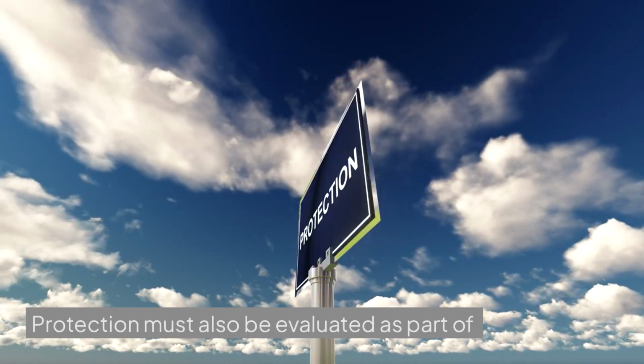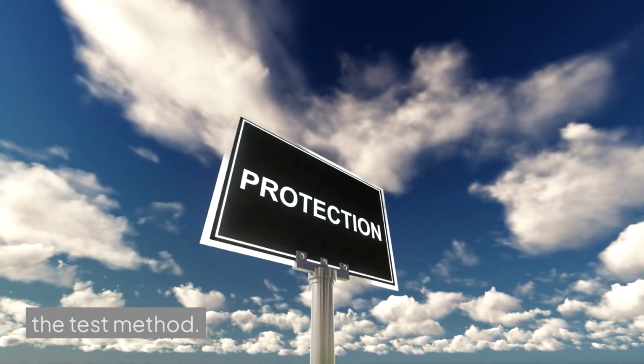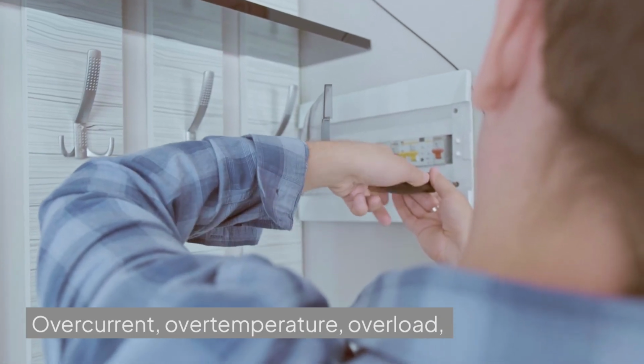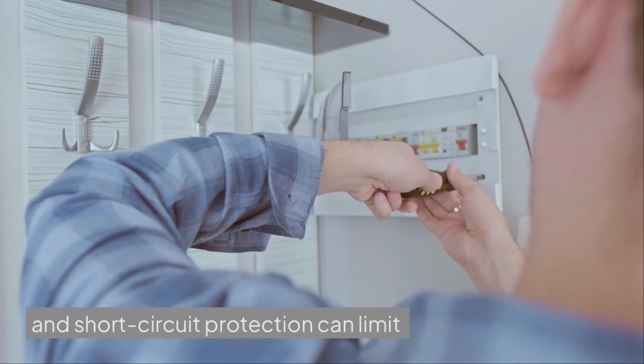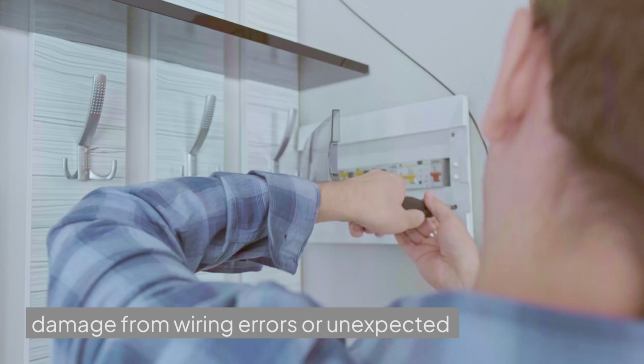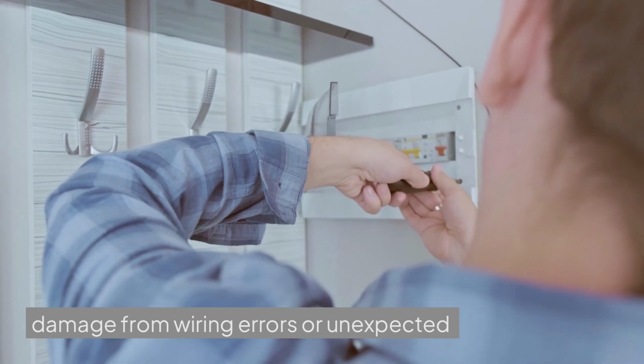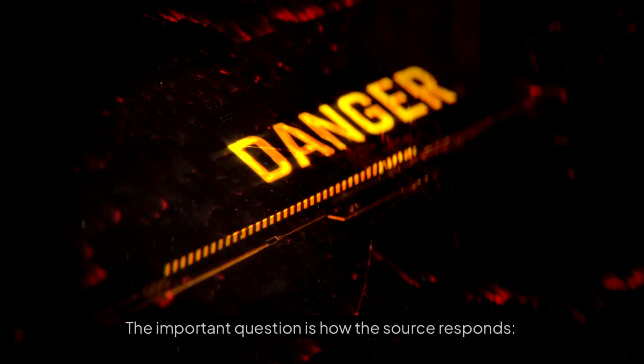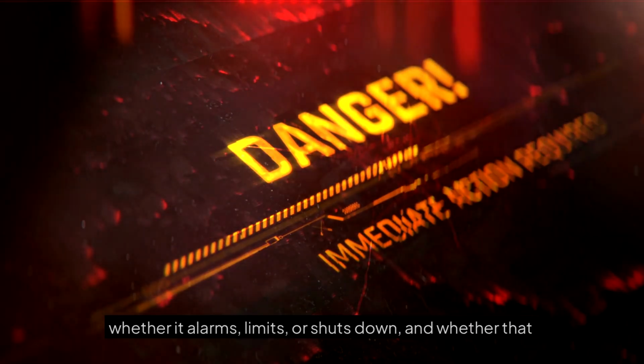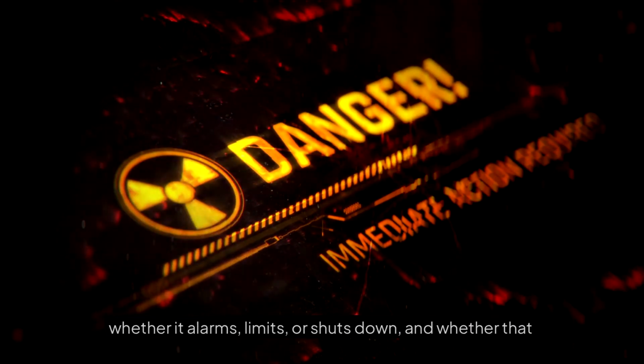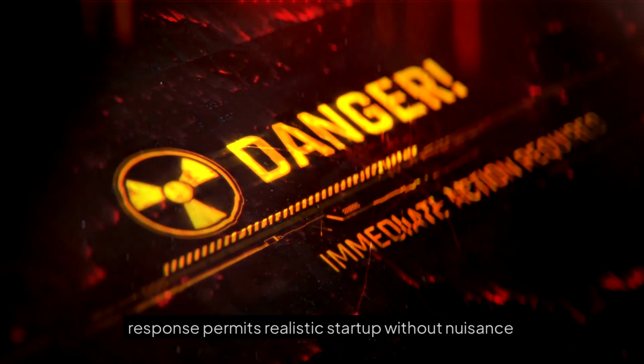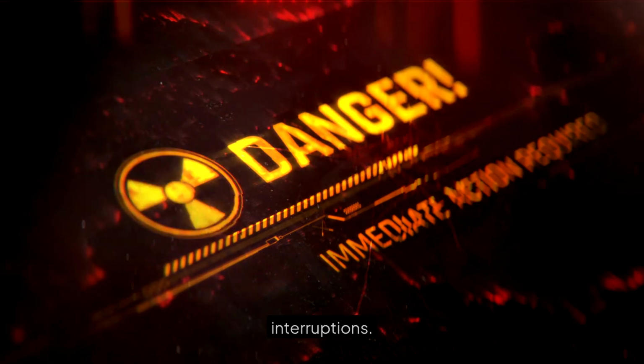Protection must also be evaluated as part of the test method. Overcurrent, overtemperature, overload, and short-circuit protection can limit damage from wiring errors or unexpected faults. The important question is how the source responds, whether it alarms, limits, or shuts down, and whether that response permits realistic startup without nuisance interruptions.